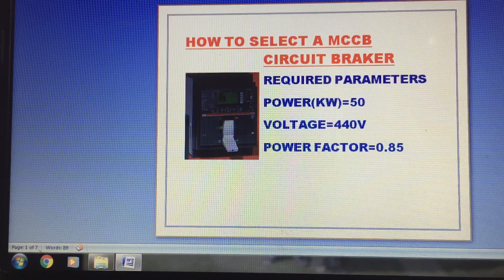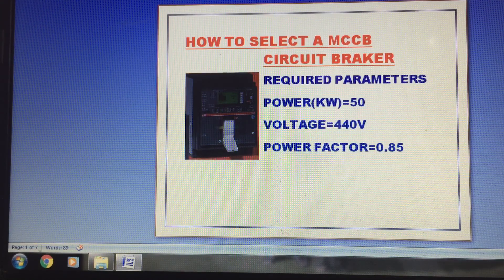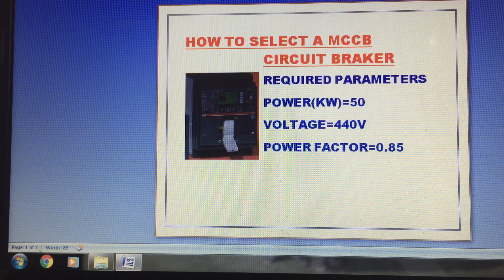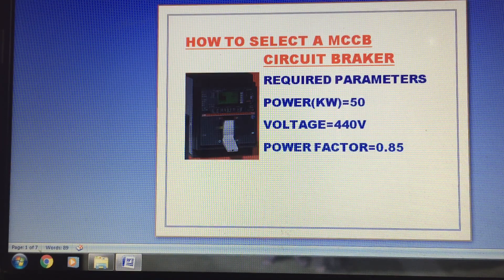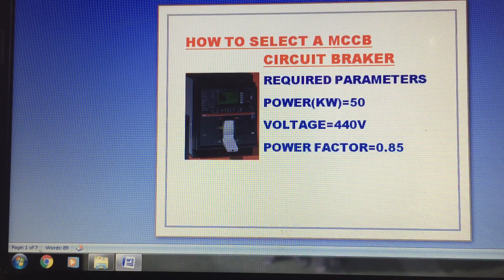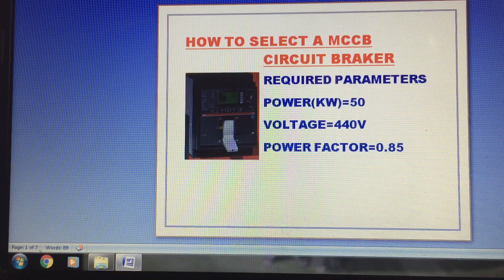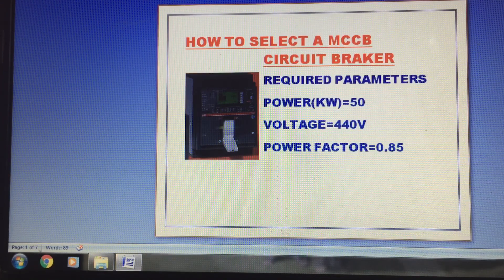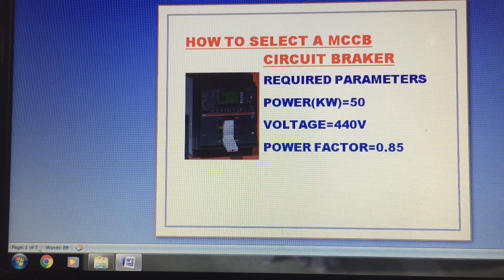How to design the capacity and design the case. In the picture, it is an MCCB breaker, and these are the required parameters. Power is approximately 50 kilowatt. Voltage is 440 volt. Power factor is 0.85.